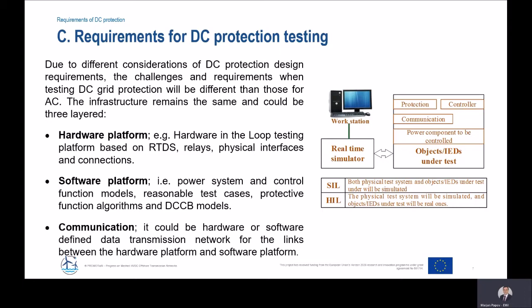Hardware platform in this context is very important, and it is also important to have real-time testing methods like RTDS, because it is not only important to see how the relay operates and what the time of operation is, but also to see how the network will perform after the DC current is interrupted. Because we still do not have a multi-terminal DC grid in practice, this is the only way at this moment to see the performance of the system itself and the converters and other components.